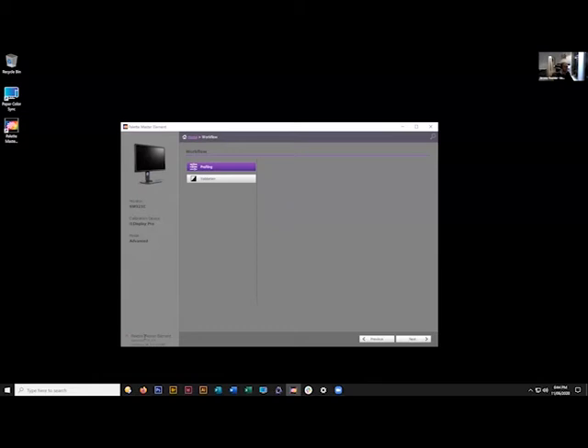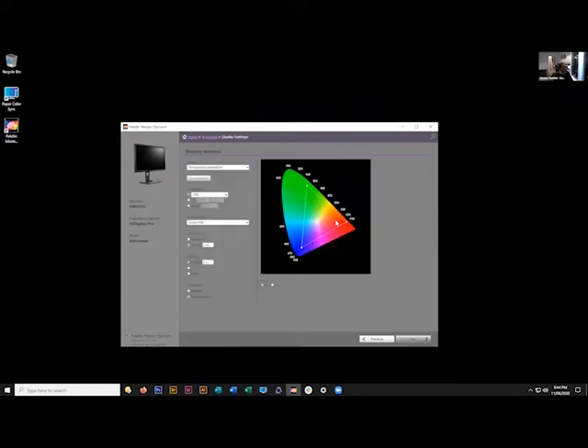Down in the bottom left-hand corner, you can see a little bit of technical information, the version of the application that we're using. We're using version 1.3.9 that was released literally a couple of days ago. BenQ are very good at doing updates. They flow through regularly. And the calibrator we're using is this i1 Display Pro, also known as the i1 Display version 3. We hit next to go to the next thing.